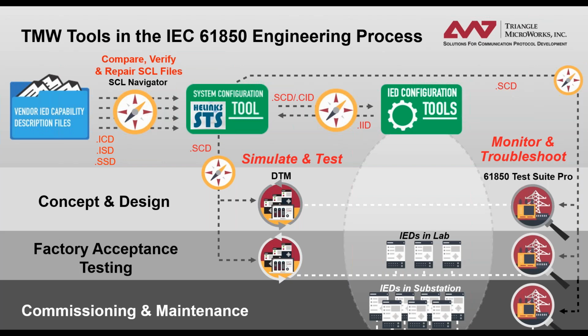Hello? Yes. Go ahead, Jörg. So generally, utilities can use this to produce the SSD file, the system specification, which they hand over to the system integrator, which then at the end gives back the SCD, and then it can also be used to compare the results of the engineering against the specification. Okay. But the system integrator can be the utility itself, or a third party, or a vendor, or whatever. Yep.